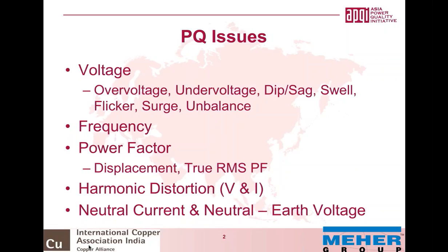The fourth issue is harmonic distortion, primarily voltage and current distortion. We could also look at demand distortion, but those are derived from these two - fundamentally it's voltage and current distortion. This means the sine wave that we believe should be there is no longer pure, but distorted due to various factors - non-sinusoidal content from contamination or corruption caused by higher frequency components, which are conducted disturbances.